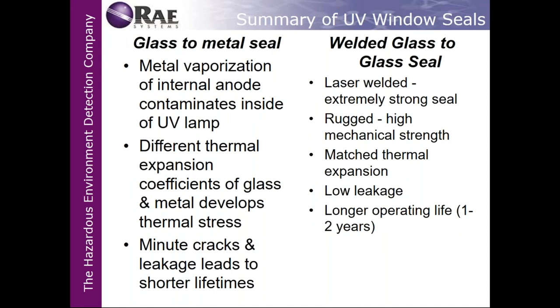We'll pass that up to you. I want you to focus on this page, the welded glass-to-glass seal. It's laser welded, extremely strong. It's rugged, has high mechanical strength. In other words, you can shake it, you can drop it, I mean, to an extent. But it should be able to handle the abuse. It has matched thermal expansion, so it's going to stay contained. It has low leakage and longer operating life. In other words, you're going to get anywhere from 1 to 2 years, even 3 years with our half-inch lamp on our MiniRAE 3000.